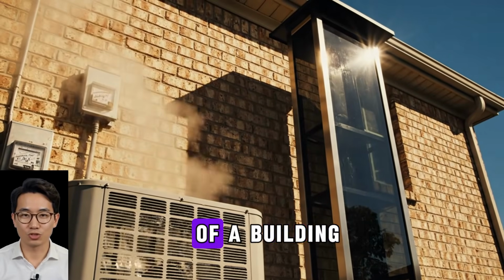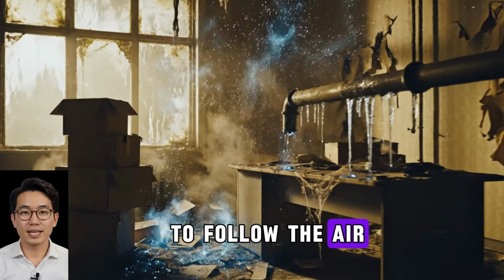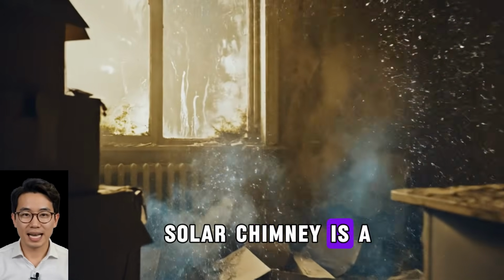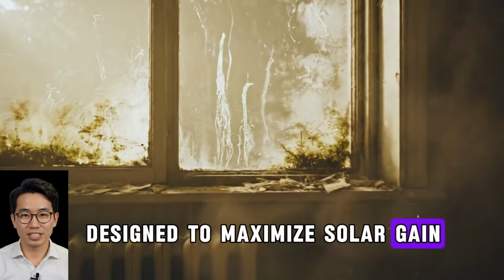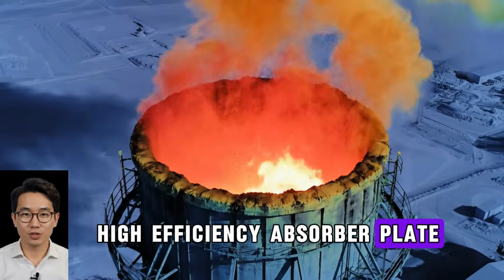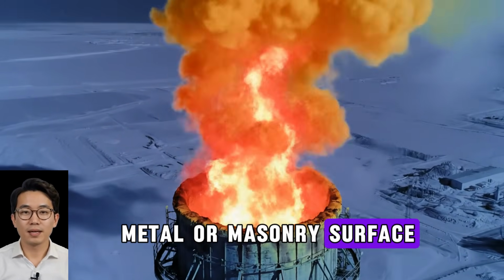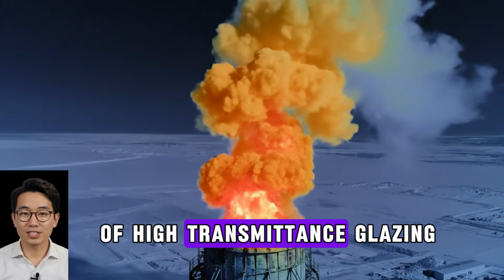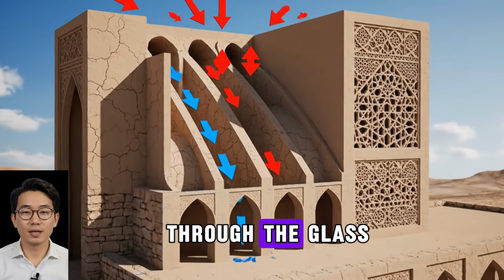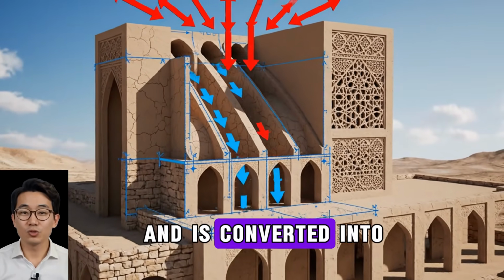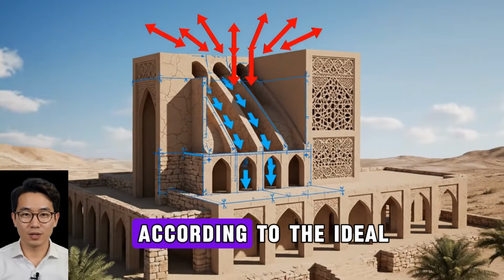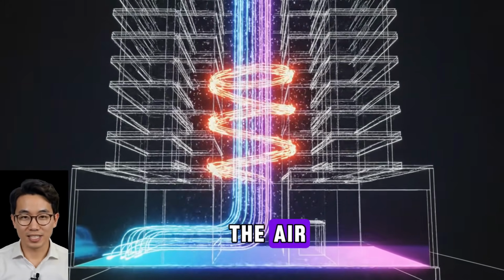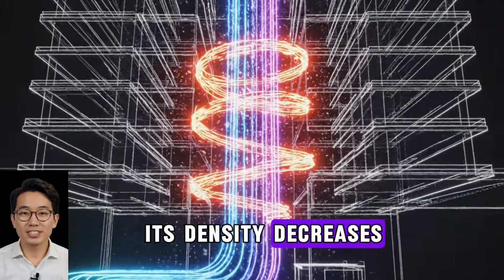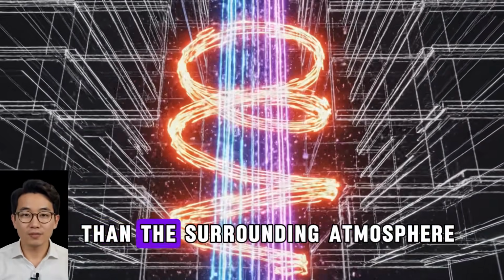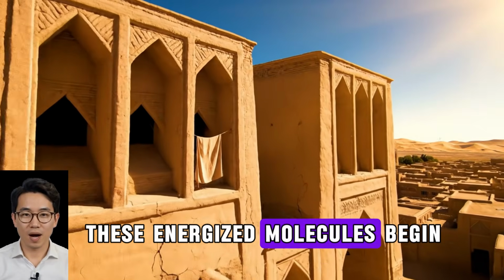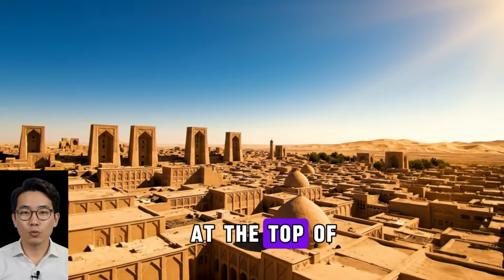To understand the engineering of a building that breathes, you have to follow the air. At its core, a solar chimney is a vertical shaft designed to maximize solar gain. It consists of a high-efficiency absorber plate, usually a dark-colored metal or masonry surface, positioned behind a layer of high-transmittance glazing. As solar radiation passes through the glass, it hits the absorber plate and is converted into long-wave thermal energy. According to the ideal gas law, as the temperature of the air inside that shaft increases, its density decreases. The air becomes lighter than the surrounding atmosphere. These energized molecules begin to rise rapidly toward the exhaust at the top of the chimney.